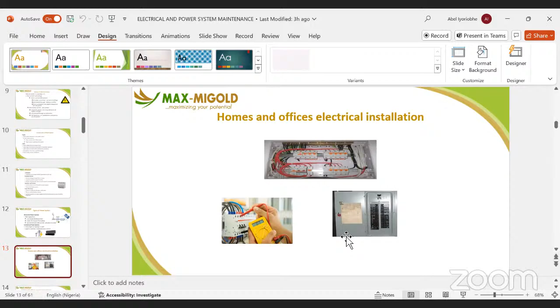And unlike the fuse, where your technician will just go and get a wire, twist it together, put it in and tell you, okay, it is working. It's working, but it's not protecting anything. You may feel the technician knows what he's doing. Actually, he doesn't know what he's doing. Because of that, a whole building can be set ablaze because the wire that he used either is overrated or is too thick for it to open when there is a fault. But a circuit breaker will trip whether you are there or not. Like I mentioned here, do not repair a circuit breaker, replace it outrightly.